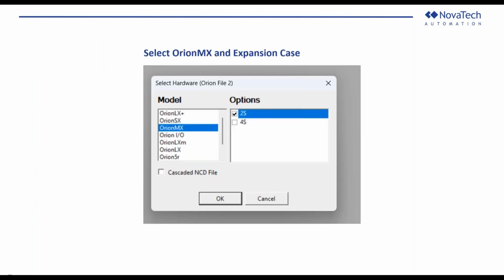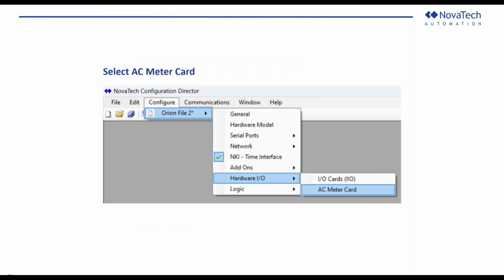You would go on NCD, select the OrionMX. I'm using 2S for my example. So I would select 2S. In case you're going with 4S, you would select that and hit OK. From there, you would go to Configure tab and then go to the Hardware I/O and select the AC meter card.